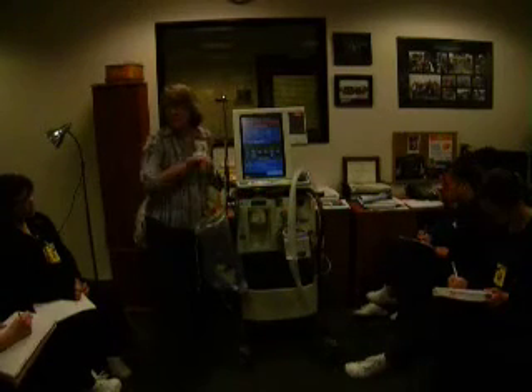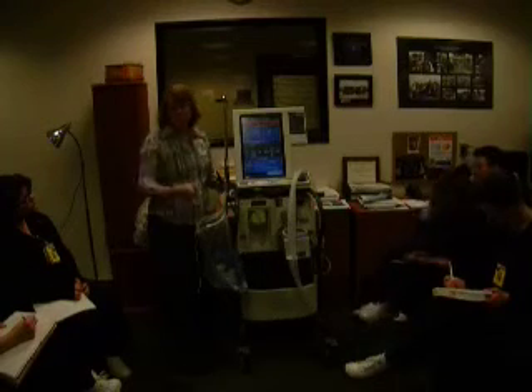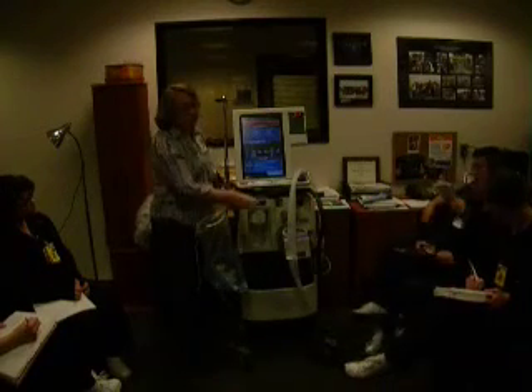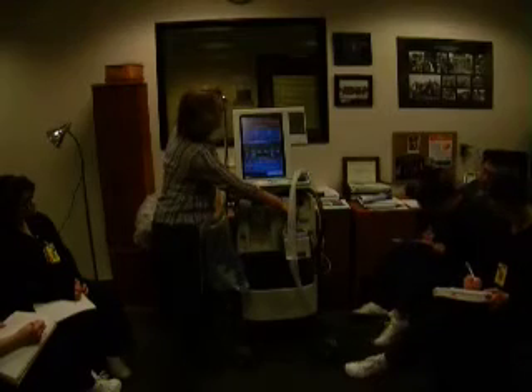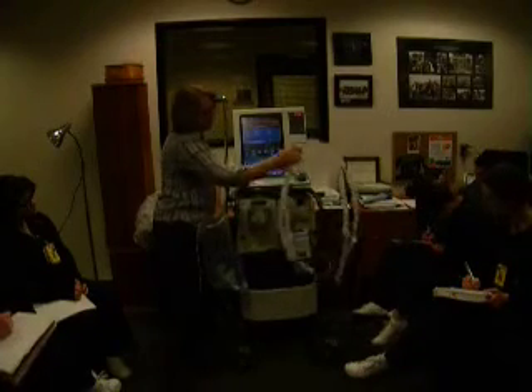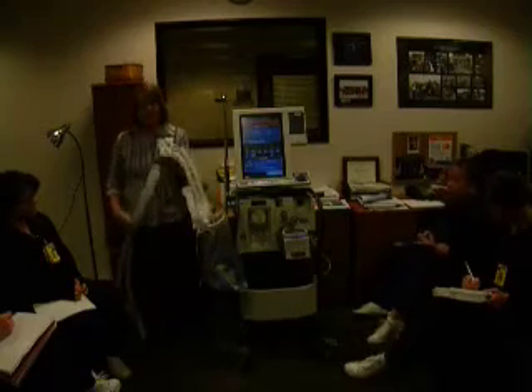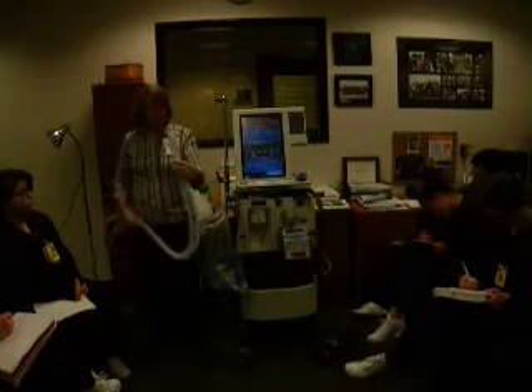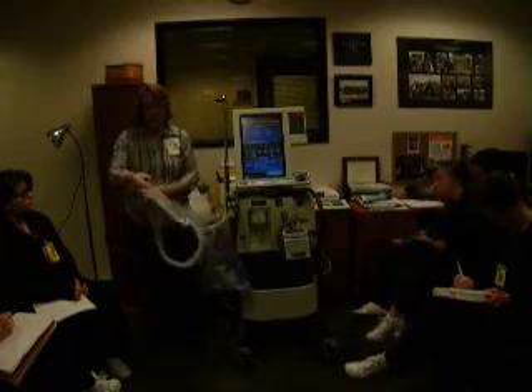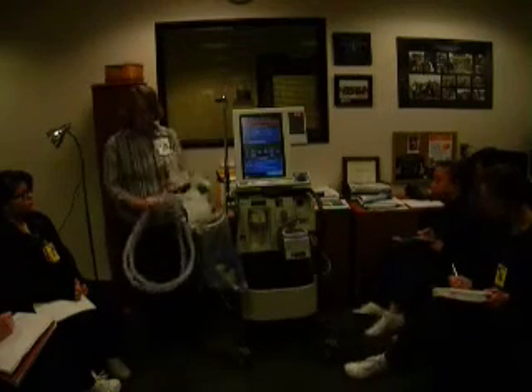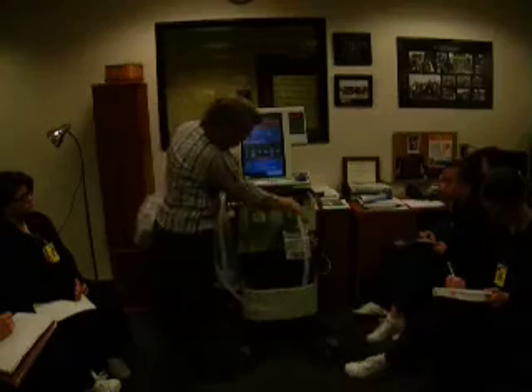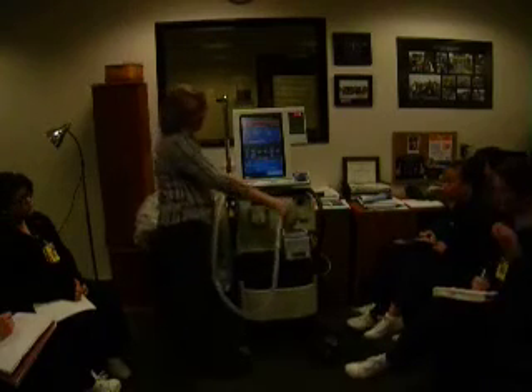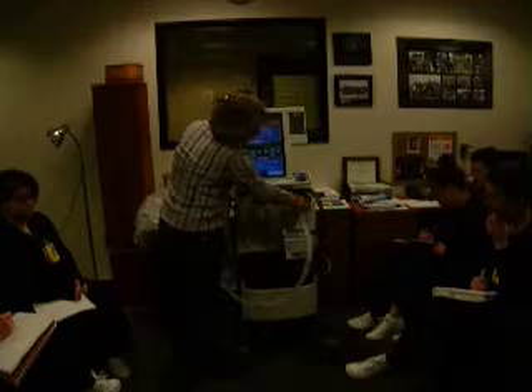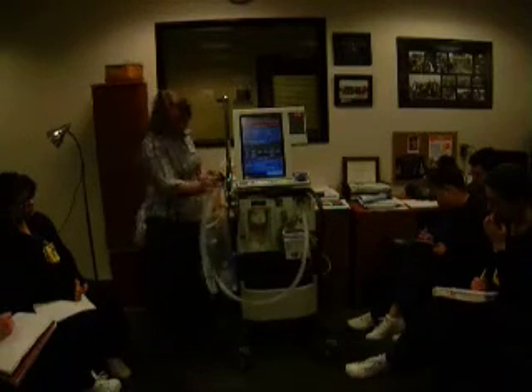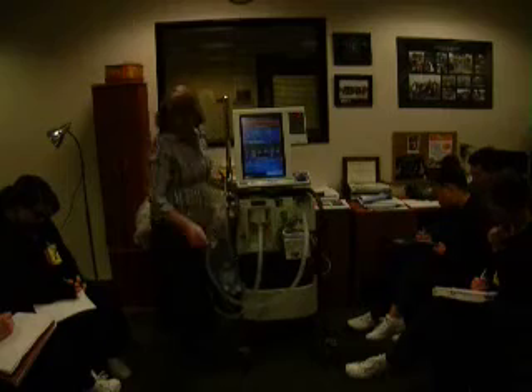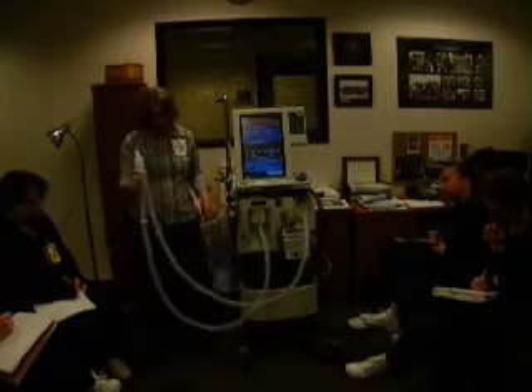And then over here you'll see to patient. Remember I was telling you guys, usually you'll see inspiratory or expiratory or to patient or from patient on your ventilator so you know which is which. This ventilator, it says right here, to patient. So we know that's our, which side? It's the one without the... Inspiratory. Which, how do we know which one is, oh, this one, it doesn't matter. Yeah, normally the one with the temp probe. Typically you'll have an inspiratory filter there, but I didn't put one on just for demo, so that would be there. And usually we'll have our humidifier picked up too. When there's a temperature probe, it's reading the inspiratory temperature, because that's the side that we're worried about.